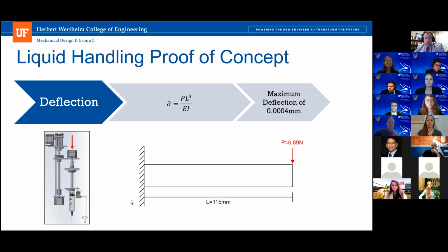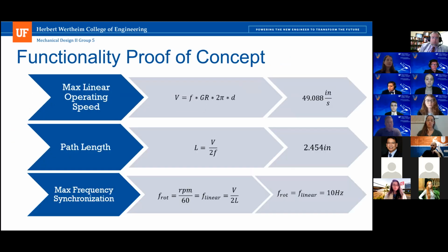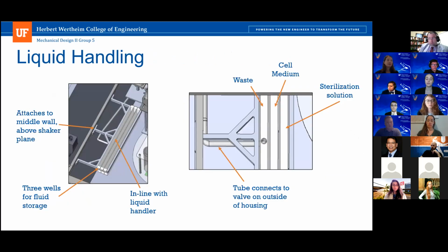What about contamination between wells and between the different well plates? Do you have any sort of system to clean or flush out as you're delivering and removing fluid from each well? So the contamination, it's partially from this film, so there's less of a risk of contamination between the wells, and then we also have this well of sterilizing solution within each chamber. So if the needle needs to be sterilized between going into each well or tube, it can come over here and sterilize with the solution. Okay.